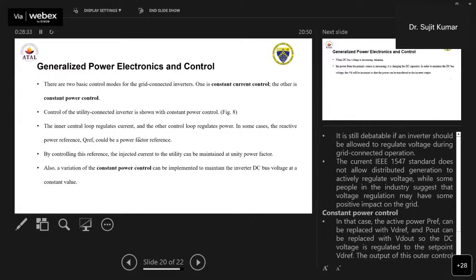In some cases, the reactive power reference Q could be the power factor reference. So there we change the power factor reference, based on the reactive power reference and how much AC side power factor has been developed, so that the voltage profile is maintained at the AC side. By controlling this reference, the injected current at the utility can be maintained at unity power factor, by varying the reactive power reference Q at that particular point.